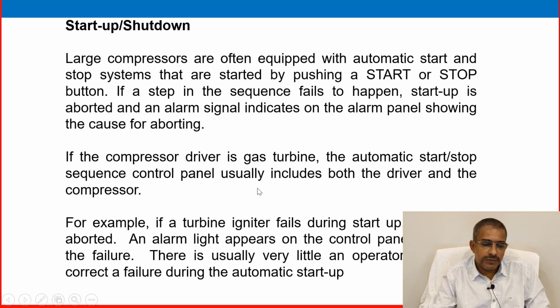Startup and shutdown. Large compressors are often equipped with an automatic start and stop system that is started by pushing a start or stop button. If a step in the sequence fails to happen, startup is aborted and an alarm signal is indicated on the alarm panel showing the cause of aborting.